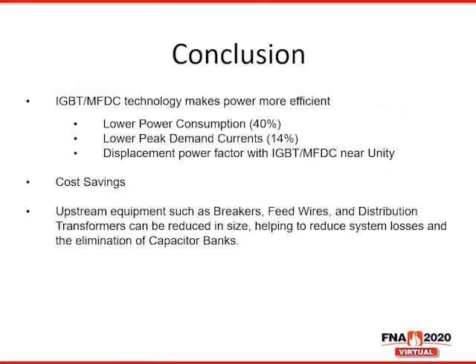In conclusion, and as a summary for this presentation, we have demonstrated a retrofit of a VRT vacuum furnace with our IGBT MFDC power supply. We observed a 40% lower power consumption in kilowatts, a 14% lower peak demand, and a displacement power factor of near unity across the entire cycle. This correlates to real cost savings for furnace applications. Some of the other things that I didn't touch on in the presentation are that there are other forms of savings with using our IGBT MFDC system, which are decreased size of breakers, feed wires, and distribution transformers in your facility.